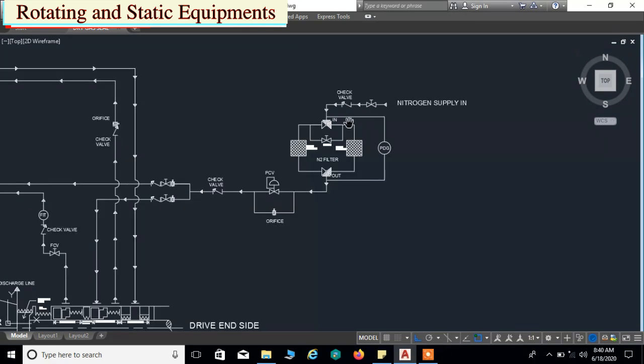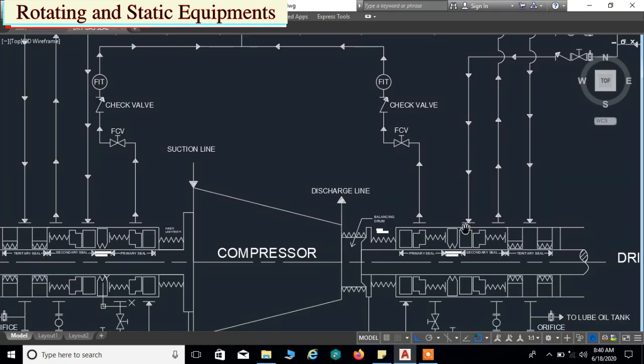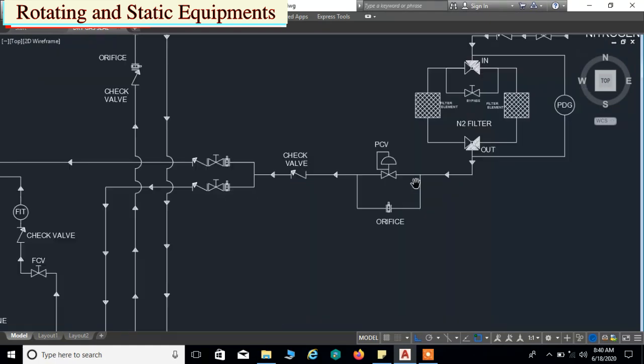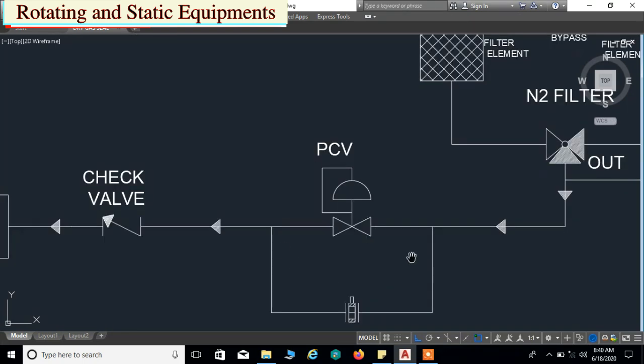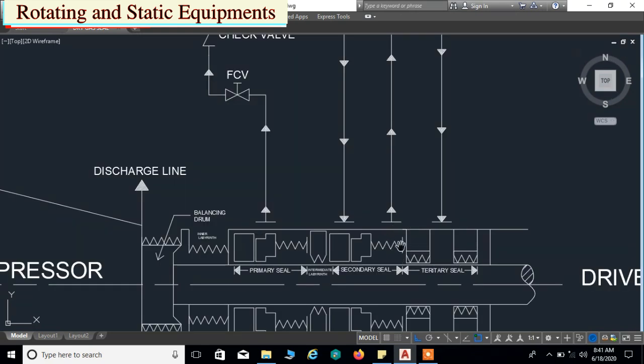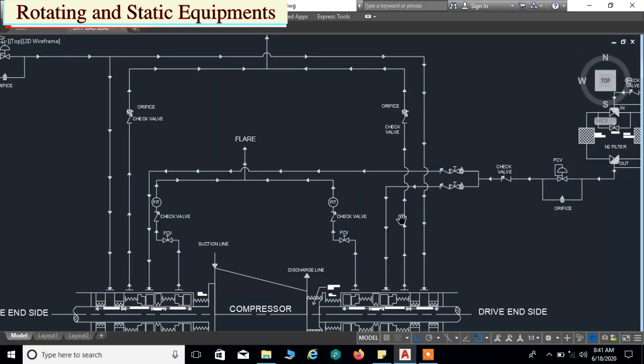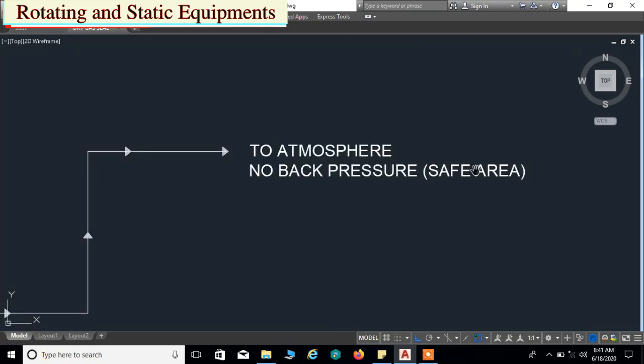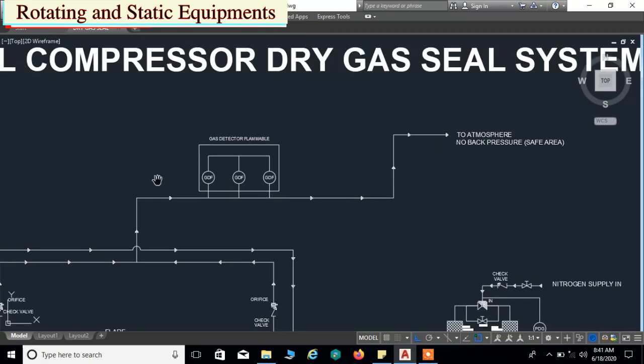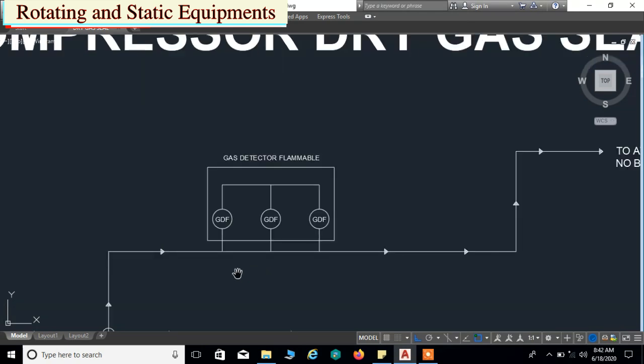Cleaned nitrogen is injected to the secondary seal chambers on the drive end and non-drive end sides through an orifice, and the nitrogen gas pressure is controlled and maintained by a pressure control valve. The nitrogen gas that returns from the secondary seal chambers is sent directly to a safe area vent. This is called the secondary venting line, and secondary venting line piping is monitored by flammable gas detectors. This provides alarm signals and trips the unit in case of leaks from the primary seal chambers.